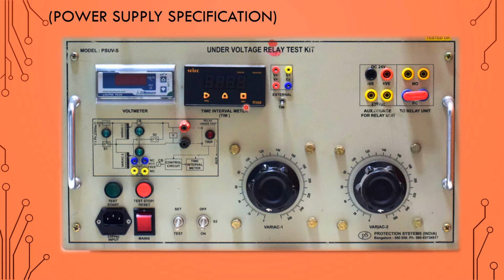This is the time interval meter, which is used to measure the trip time. And here you have to set the timer switch to timer mode, not external mode, so that the time interval meter will synchronize with the circuit breaker. And here no timer switch is there, so this is blank. Then the auxiliary supply terminals: here we need 24 volt DC. These two terminals will be used to feed the auxiliary power supply to the under voltage relay.